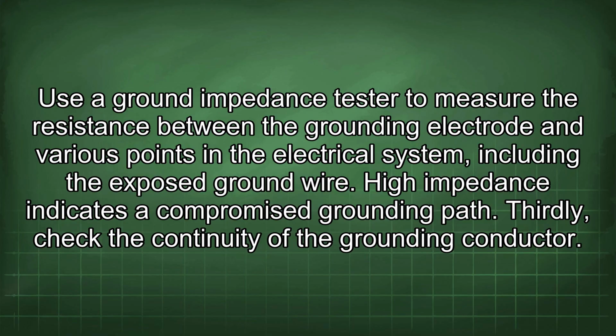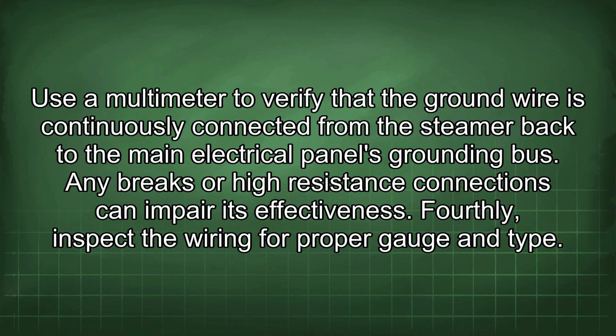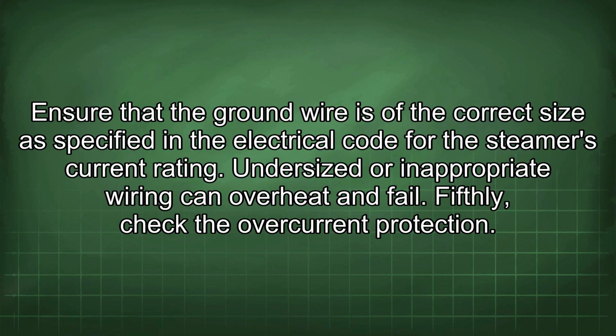Thirdly, check the continuity of the grounding conductor. Use a multimeter to verify that the ground wire is continuously connected from the steamer back to the main electrical panel's grounding bus. Any breaks or high resistance connections can impair its effectiveness. Fourthly, inspect the wiring for proper gauge and type. Ensure that the ground wire is of the correct size as specified in the electrical code for the steamer's current rating. Undersized or inappropriate wiring can overheat and fail.